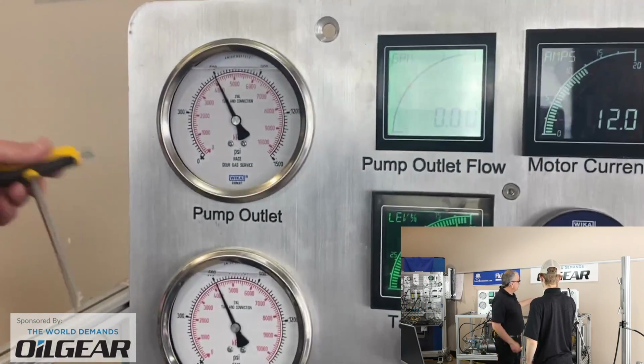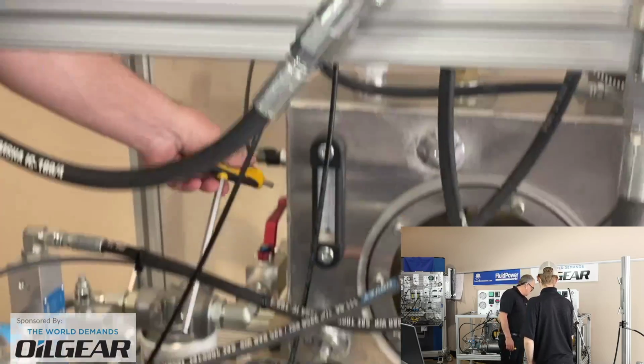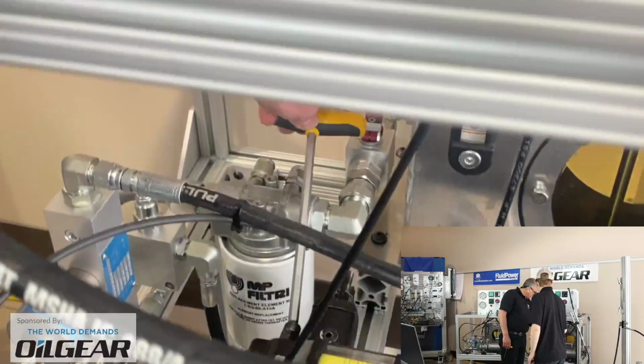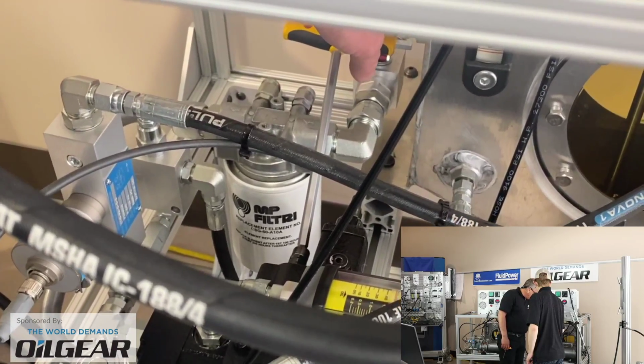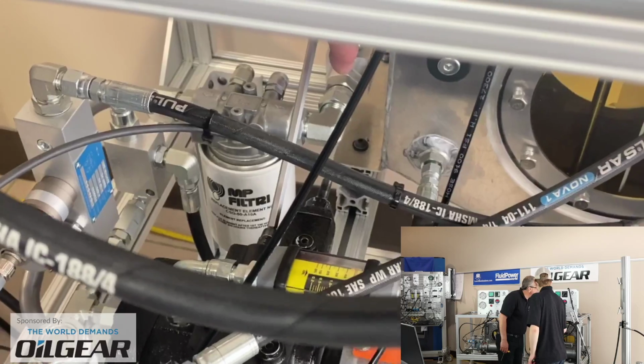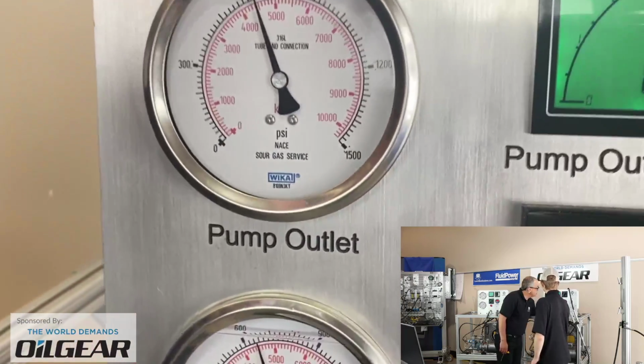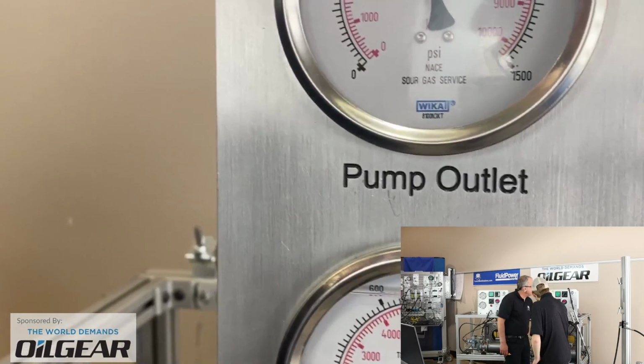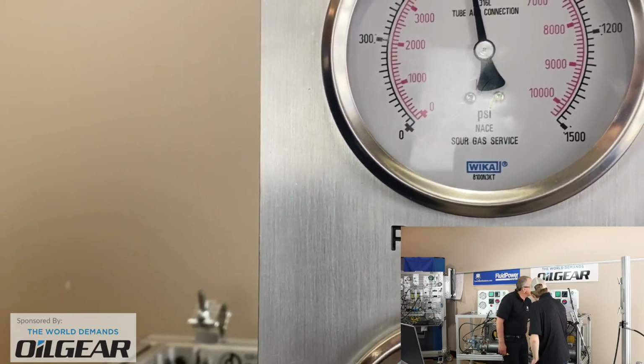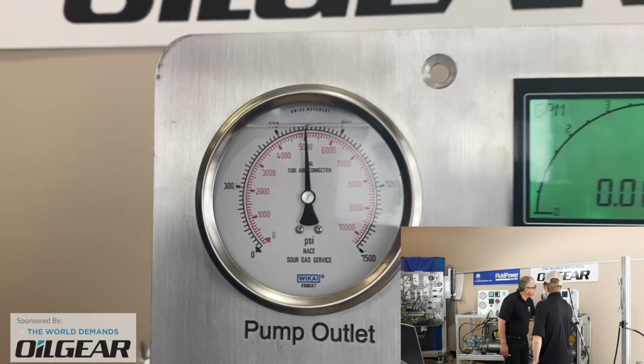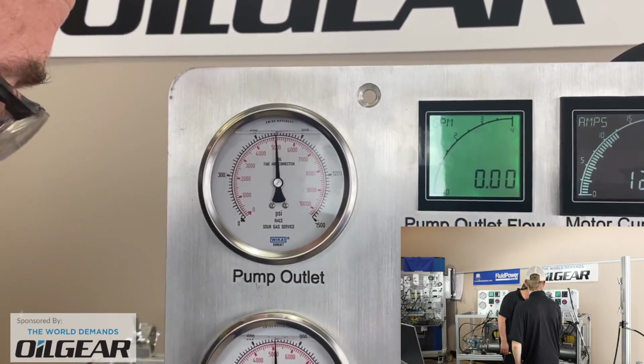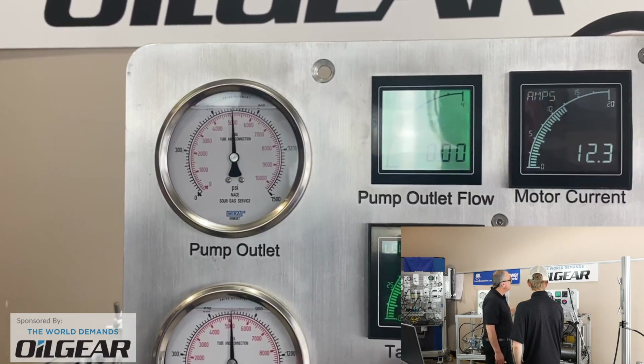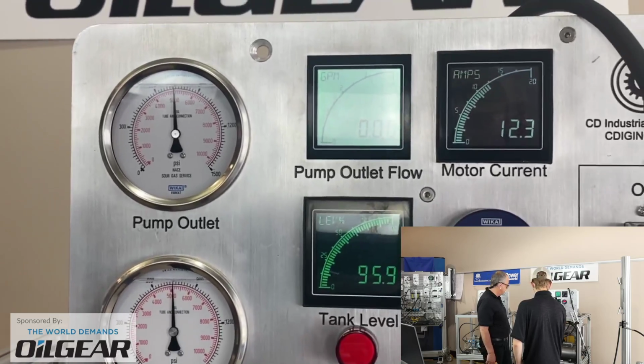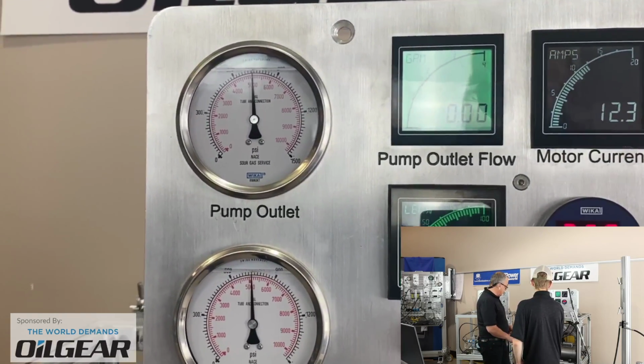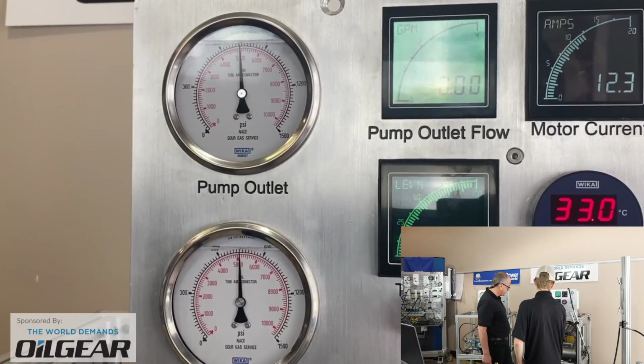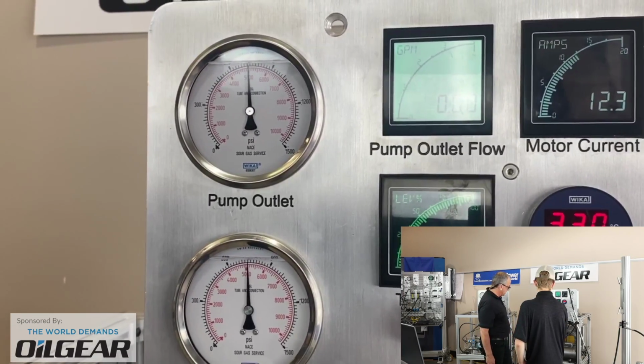And so now, if it's perhaps supposed to be 750 psi, with the jam nuts backed off and loosened, I take my hex key to that pressure compensate control on the opposite side of the pump and turn clockwise to increase the maximum system pressure, adjusted when flow has been blinded out, up to 750 psi, and that was less than 1/4 of a turn to make that 150 psi change. And again, adjustment should be made at a nominal system operating temperature, but it's not too much more complicated than what you've seen.